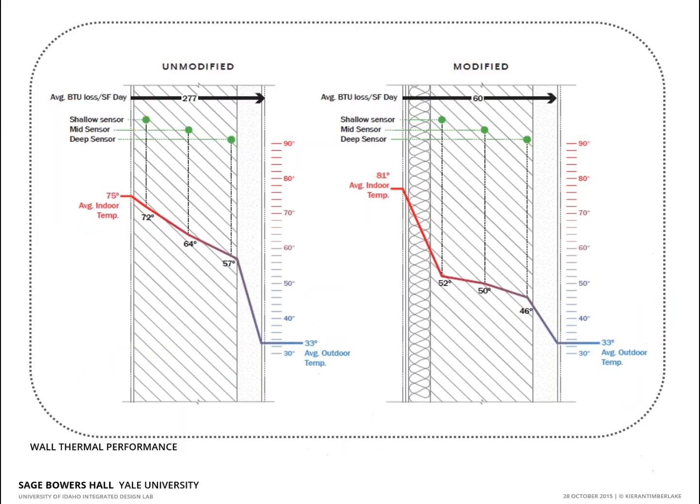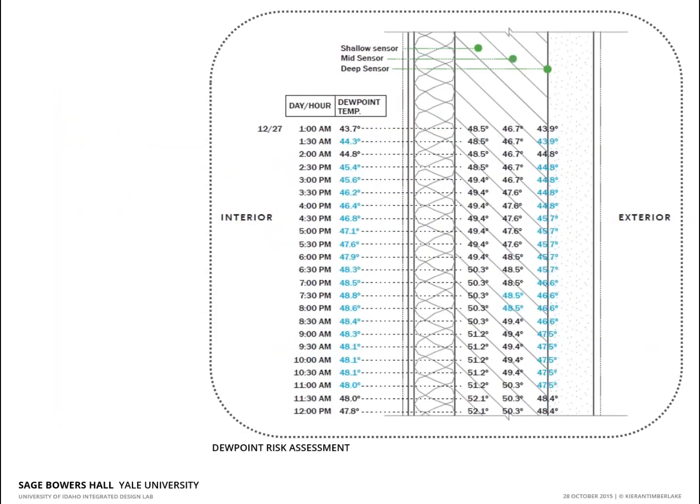Using this information, we were able to assess temperatures over the course of a winter, where we could see with the addition of insulation, the obvious happened. We saw a lot lower temperatures in that envelope. But while this was certainly indicating that the performance that we wanted was there, it did indicate a couple of things of note. One is that our temperatures on the inside became quite high, but also we were finding that our dew point was indeed migrating inwards inside that building, and at times the dew point temperature would coincide with freezing temperatures. So we were seeing, when you started to insulate these buildings, you were starting to see a cooling down of that masonry and the risk of having basically a freeze-thaw incident.